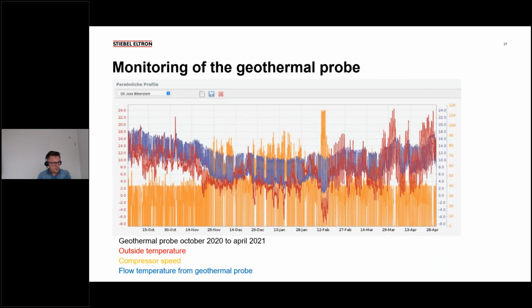What you see here, I probably don't see the blue thing. The blue means that's the flow temperature from the geothermal probe. It's just the lower part of the curve. So you see we start in winter, maybe at the beginning of winter with 10 degrees, and then it goes a little bit back and back and back. And middle of winter or end of winter, it's like 4 degrees C in the geothermal probe flow temperatures. So still a lot higher than we indicate on the data sheet. It's just 0 degrees on the data sheet. So the efficiency is a lot better than on the data sheet.